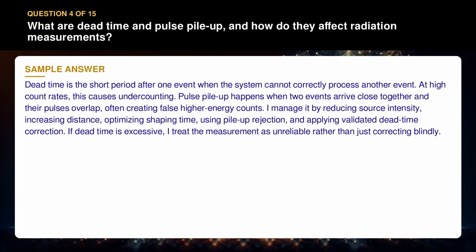I manage it by reducing source intensity, increasing distance, optimizing shaping time, using pileup rejection, and applying validated dead time correction. If dead time is excessive, I treat the measurement as unreliable rather than just correcting blindly.